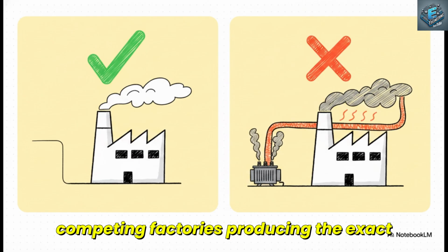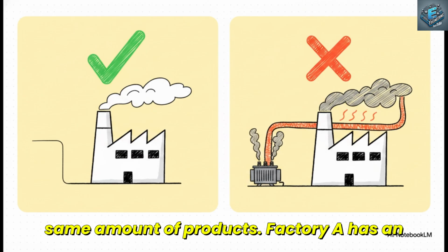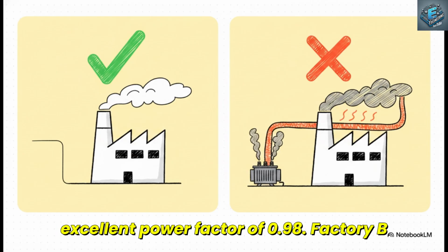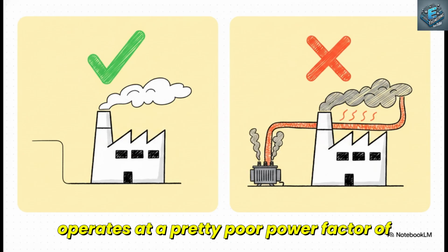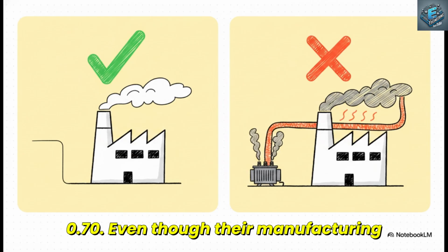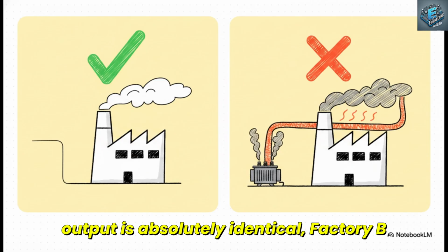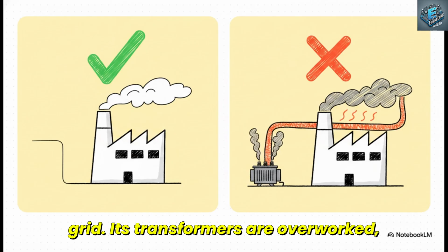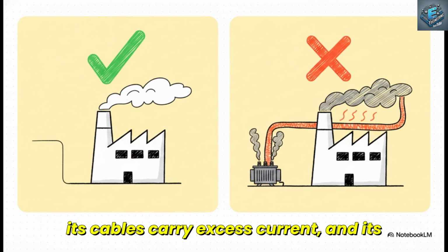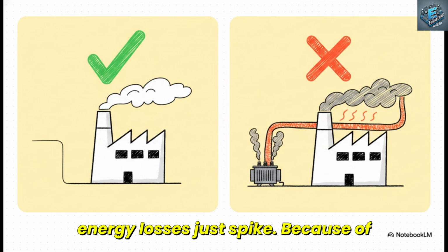Let's look at two competing factories producing the exact same amount of products. Factory A has an excellent power factor of 0.98. Factory B operates at a pretty poor power factor of 0.70. Even though their manufacturing output is absolutely identical, Factory B requires vastly more current from the grid. Its transformers are overworked, its cables carry excess current, and its energy losses just spike.